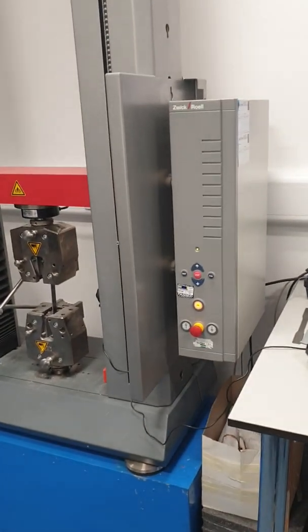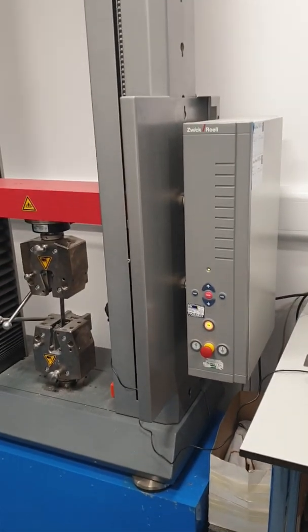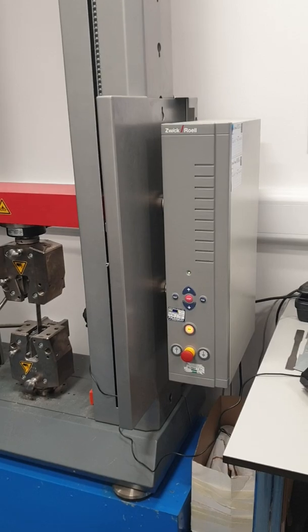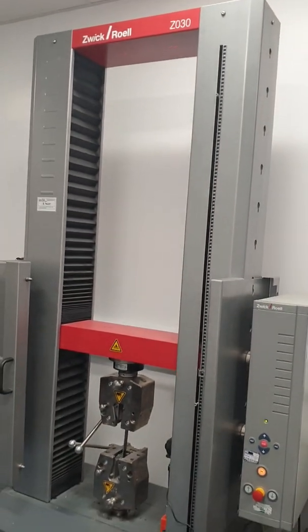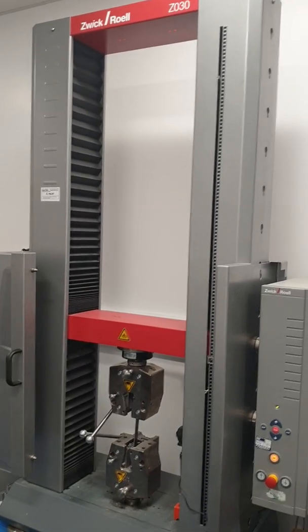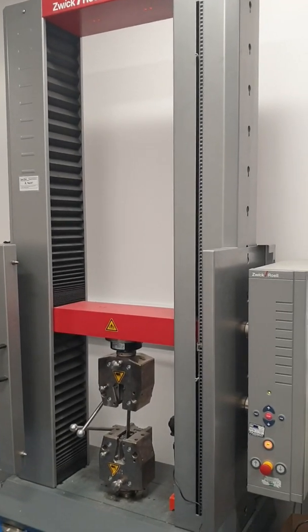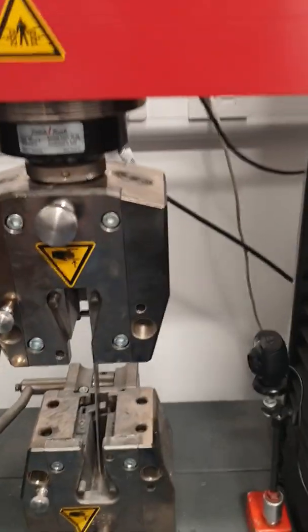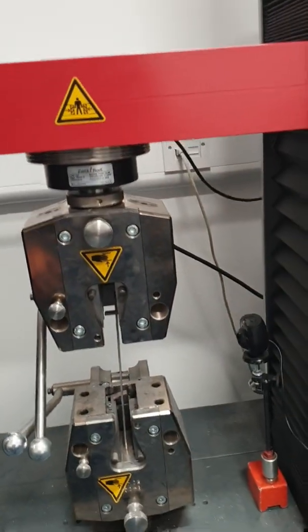Okay, everyone. Good afternoon. This is a Zwick Roell machine which we use to do the tensile testing. It's a Zwick Roell Z030, which means it can apply a load of 30 ton. We put the specimen in here. These are the two jaws.